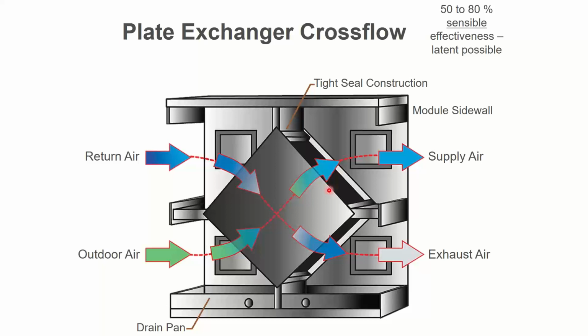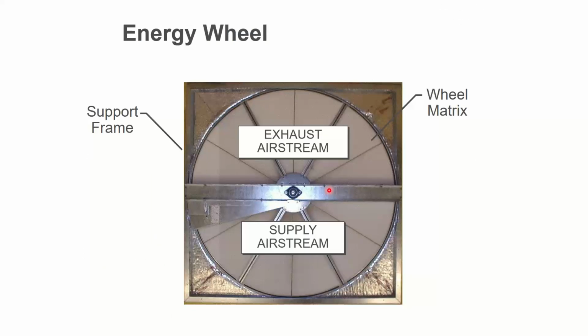And they're each just warming up or receiving heat from a metal plate. And then if they're in enthalpy style, then there's also a fibrous material between them that wicks the moisture through with vapor pressure. And then we have an ERV wheel, which is very common also. This guy absorbs BTUs in one airstream and then rotates the wheel to the other airstream.